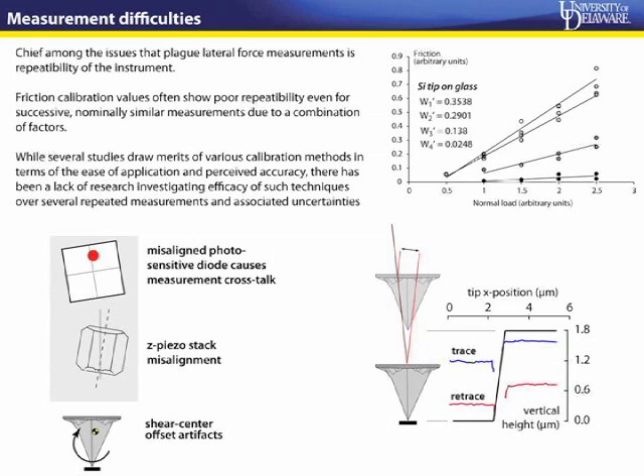One of the other things about an AFM is that it is really susceptible to changes in the output you get just based on the state of the system. This has been pointed out by a few authors. If you think about the piezo, if the tip moves up and down in AFMs where the laser position does not change, what are called standby probe AFM systems, you notice that even if you change the Z height of the piezo, you're shifting the position of the laser incident on the photodetector. So if you think about a measurement that you perform today, and tomorrow your Z piezo position is different, you're going to end up with different numbers. And that's one of the key things with lateral force measurement calibration methods.